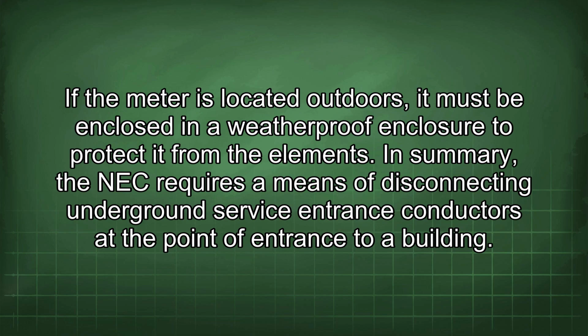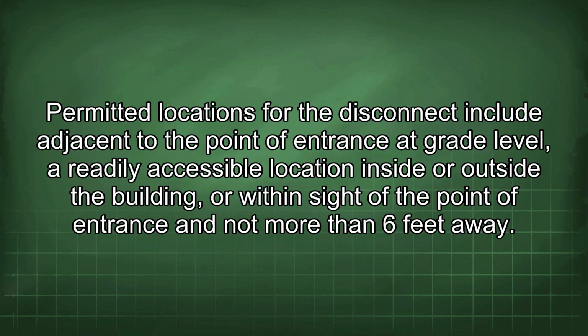In summary, the NEC requires a means of disconnecting underground service entrance conductors at the point of entrance to a building. Permitted locations for the disconnect include adjacent to the point of entrance at grade level, a readily accessible location inside or outside the building, or within sight of the point of entrance and not more than 6 feet away.